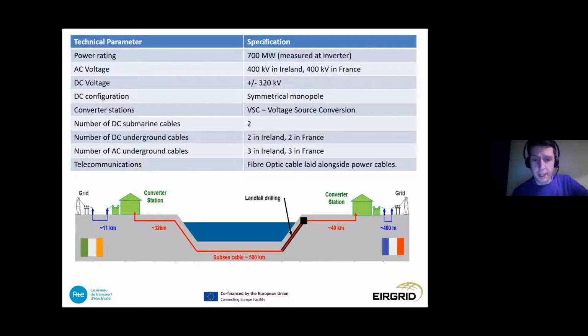The AC voltages to connect the grids will be 400 kV in Ireland and 400 kV in France. And the DC voltage of the interconnector portion will be 320 kV, which could be considered almost an industry standard for a power transfer capacity of 700 megawatts to 1,000 megawatts. In terms of the technology, VSC or voltage source converter technology was identified as the preferred solution based on the low short circuit ratios at the Irish and French transmission system connection points. VSC schemes can operate in completely passive systems with no generation, zero fault level, and or zero short circuit ratios.